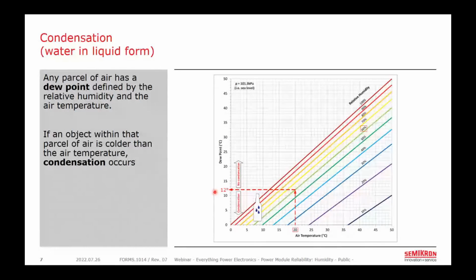So what that means is that any object in the environment that is 12 degrees Celsius or lower will have condensation form on it. So the bottle of liquid that you take out from the refrigerator and put into that 20 degrees C room might be 10 degrees Celsius, and you'll have water condense from the surrounding air onto the bottle. But conversely, if you had only left that bottle in the refrigerator for a short time and it had only cooled to maybe 15 degrees Celsius, no condensation would form.